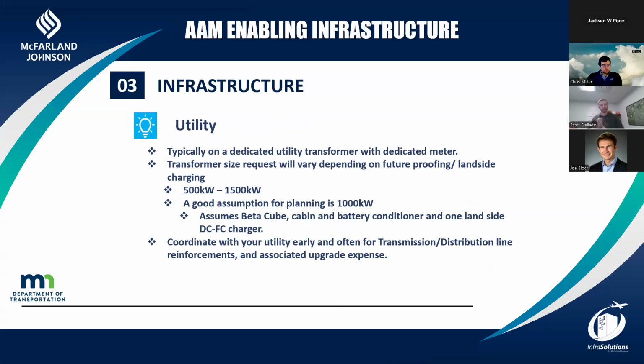Next is your utility. All of the designs we've done have had a dedicated utility transformer, dedicated meter. Your transformer size will vary depending on your future proofing and your landside charging, but you're going to be somewhere in between a 500 kilowatt if you're not planning for battery conditioning and cabin conditioning, or up to 1,500 depending on what you want for landside vehicle charging. A good assumption at a planning level is 1,000. This will get you the Beta Cube, cabin, battery conditioner, and a landside DCFC. So if you're at a planning level, 1,000 kilowatts is a good reference point.